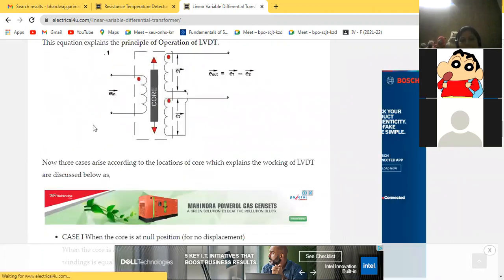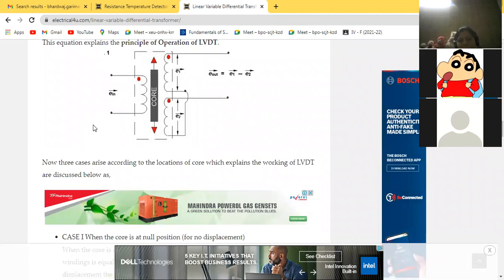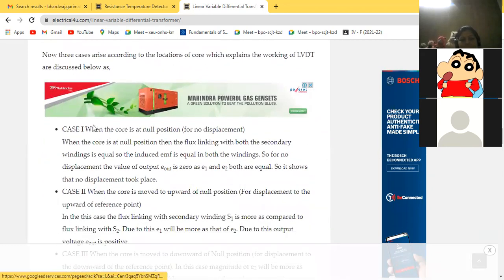Now three cases arise according to the locations of the core, which explains the working of LVDT. Case 1, when the core is at null position, that is for no displacement. When the core is at null position, then the flux linking with both the secondary windings is equal. So the induced EMF is equal in both the windings. So for no displacement, the value of output E out is 0, as E1 and E2 both are equal. So it shows that no displacement took place.